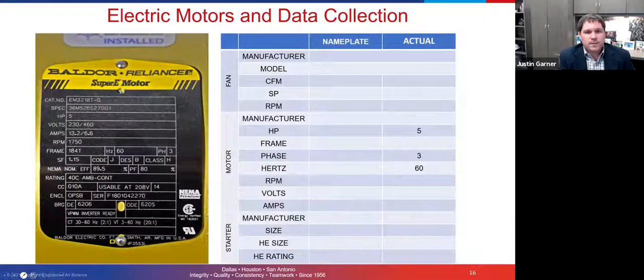All right, so let's get into some actual practical skills here. Let's talk about what we need to be collecting when we're out in the field and we're looking at electrical motors. I've got a graphical representation here of an old school data form. You can see that we have a nameplate column, we have an actual column here, and we're looking at a nameplate of a motor. Our manufacturer in this particular case is Baldor. Baldor is a very well-known motor, very popular in the HVAC industry, among many others. We've got a horsepower rating here of 5 horsepower. The frame size is 184T.